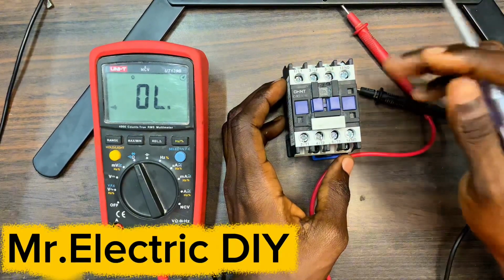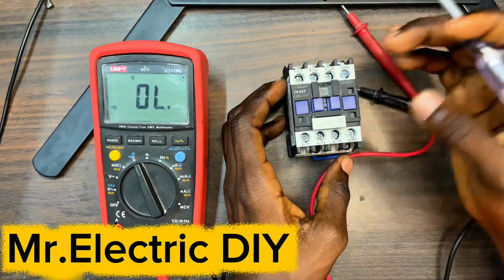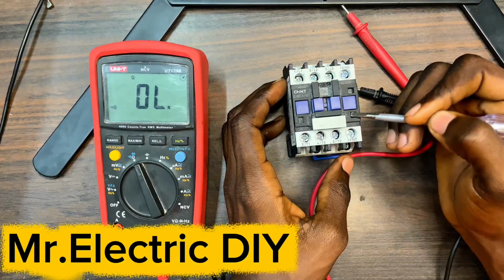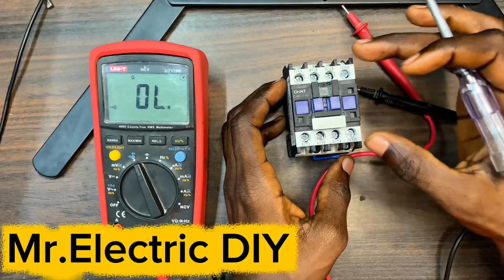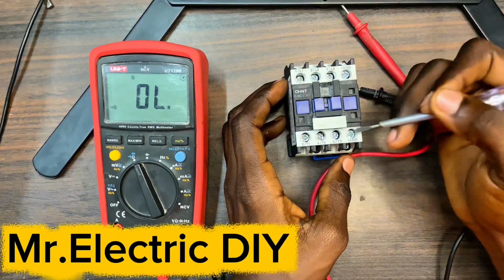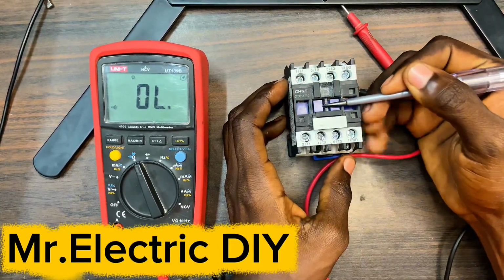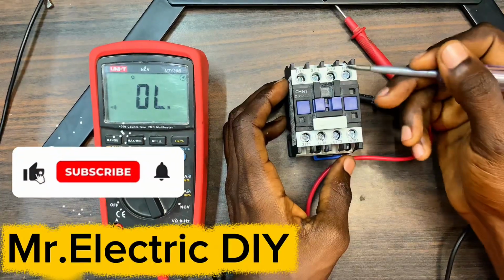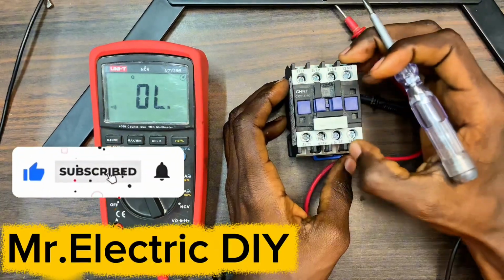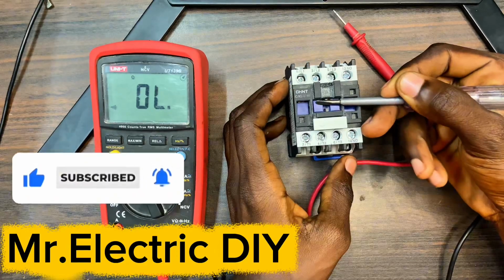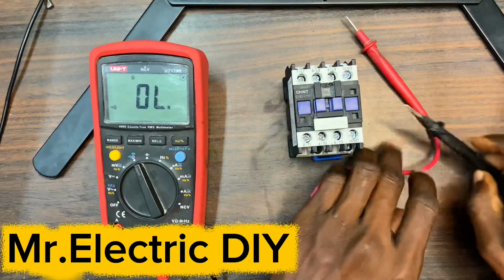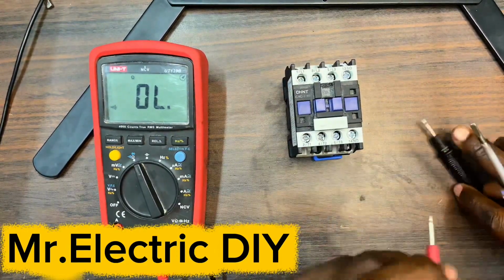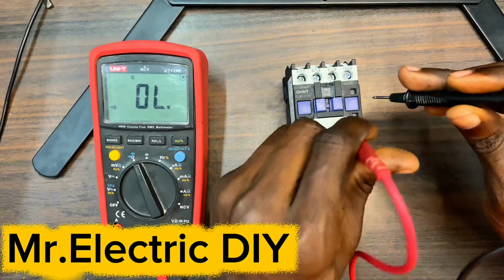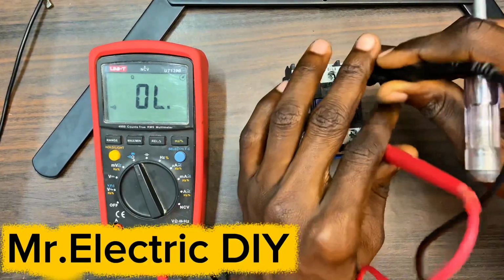Now, in order for us to check this helping terminal that it is surely normally open, what I have to do is to connect the probes to 13 and 14 and also push the plunger. This is open. So in this state, it is open. When I push it, it's going to close in that order. What I will do is to connect it to this side and this side.